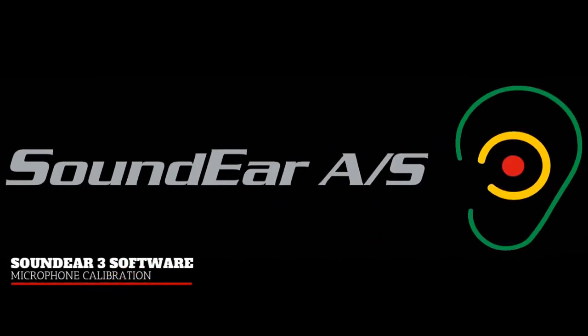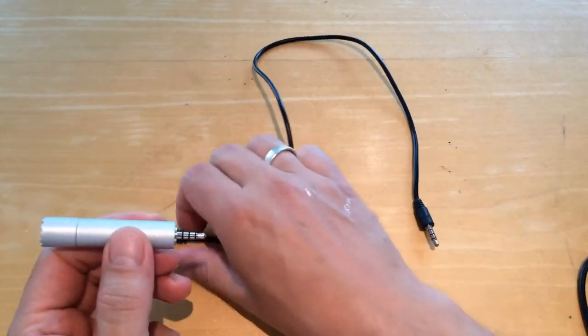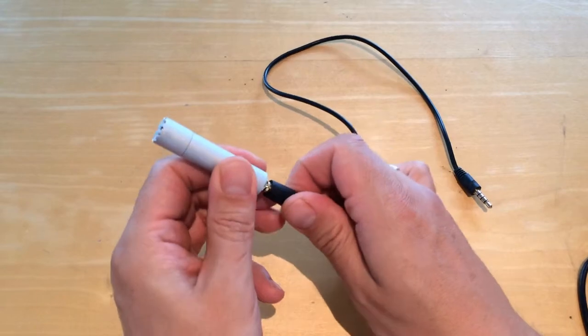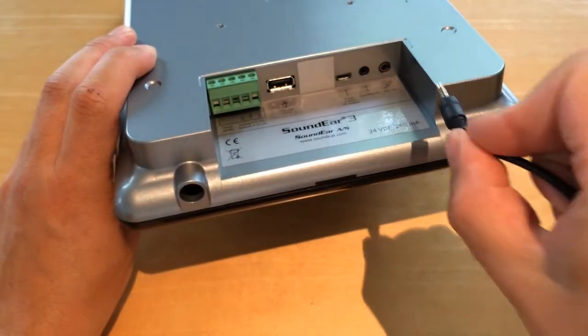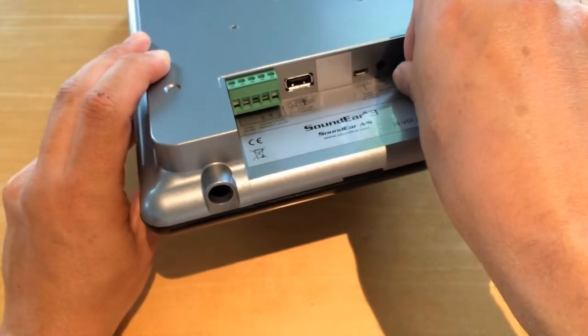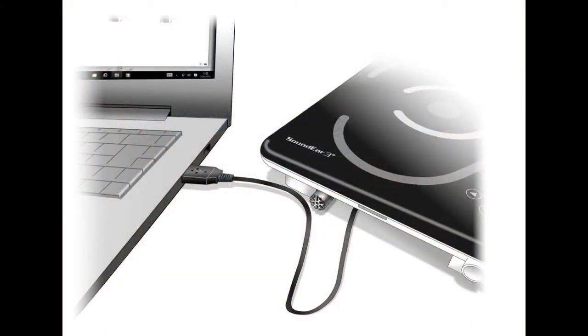This video will demonstrate how you calibrate the microphone for your SoundEar 3 device using a Type 2 calibrator and the SoundEar software. Connect the microphone to the extension cable and connect the cable to the microphone port in your SoundEar 3. Then connect your device to your PC and open the SoundEar software.